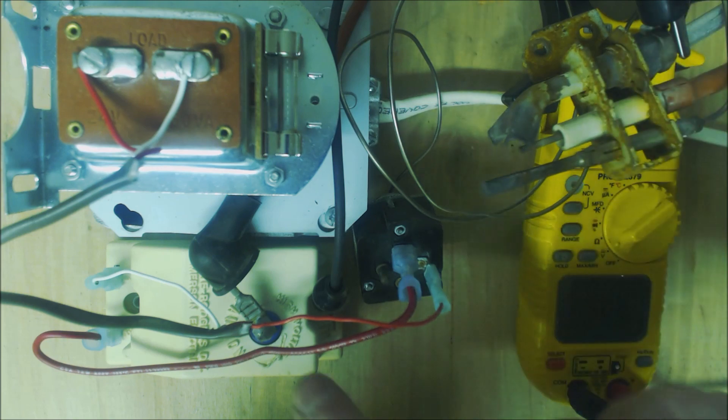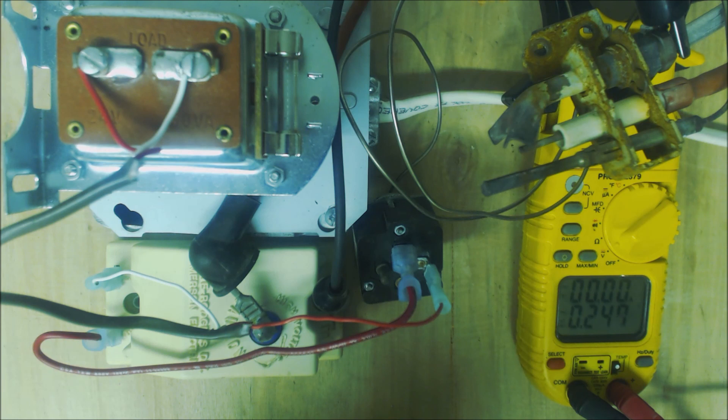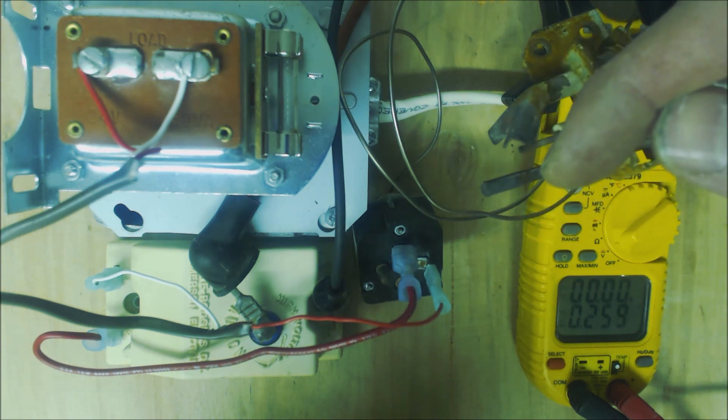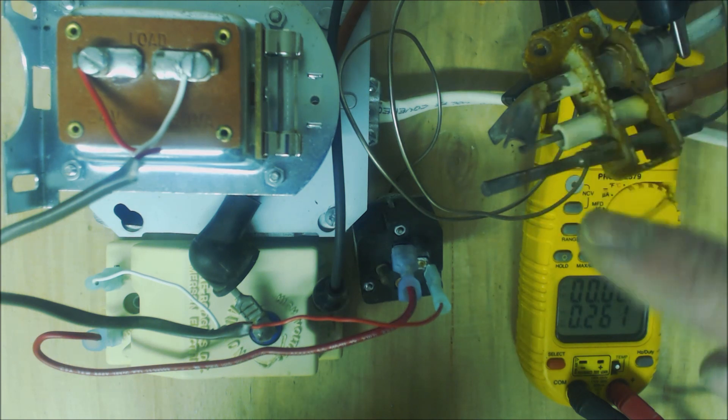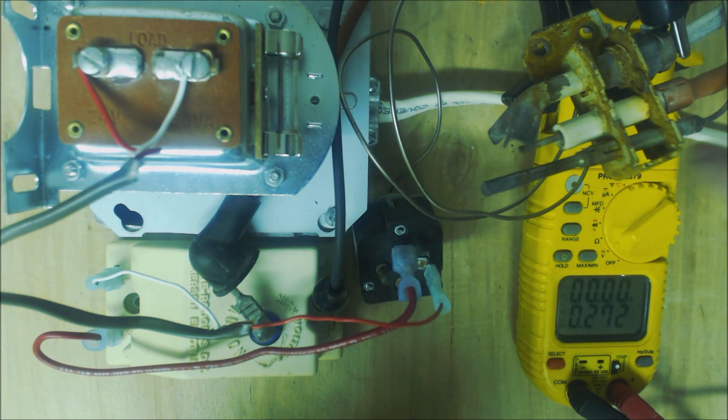At the same time this is getting power, we'll have two power wires coming over to the pilot valve. It's going to send gas through the pilot tube and the spark is going to ignite it. Once ignited, the mercury filled rod heats up, sending pressure through this rod back to the mercury switch, opening these contacts and closing these contacts.